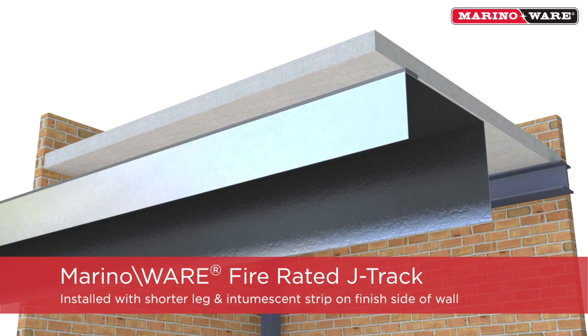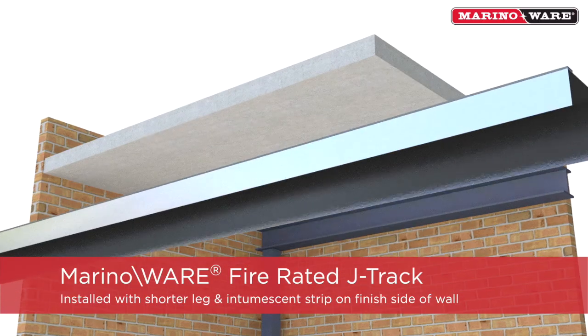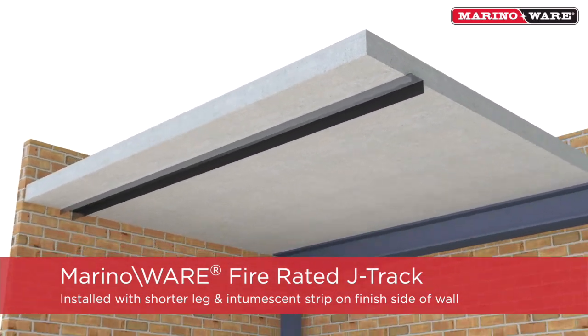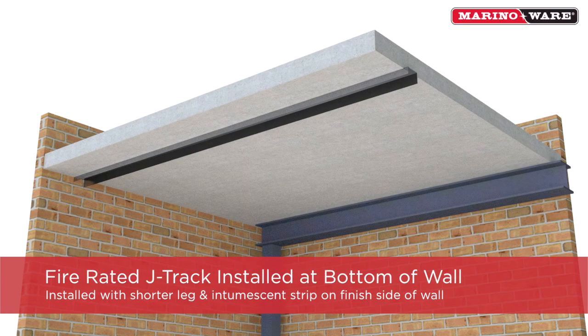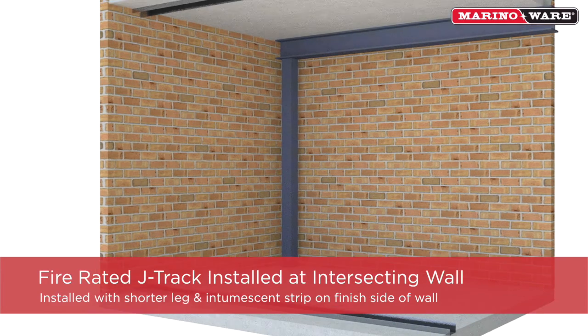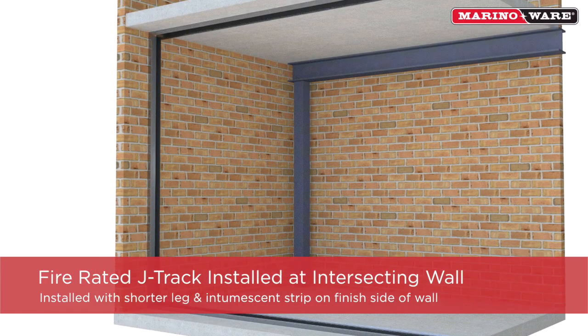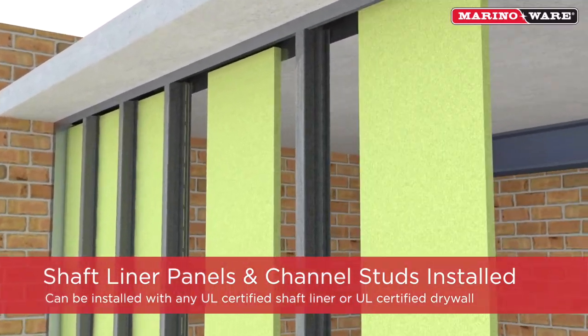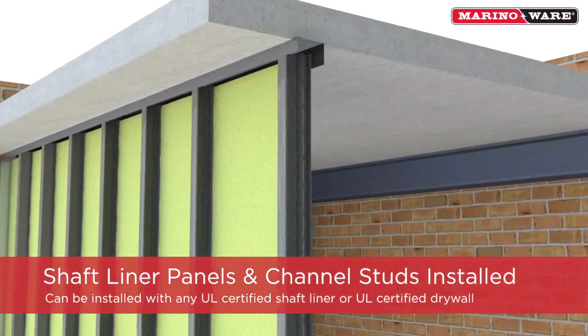The MarinoWare Fire Rated J-Track is installed with the shorter leg that has the intumescent strip on the web on the finish wall side, followed by installing J-Runner Track to the bottom and vertically against the intersecting wall. Once the J-Runner is installed, the shaft liner panels and shaft wall studs can be installed.